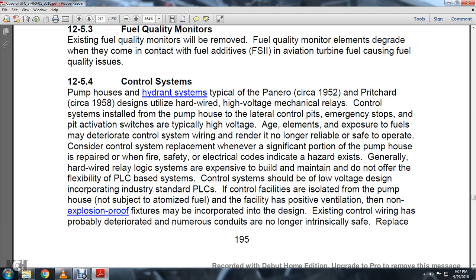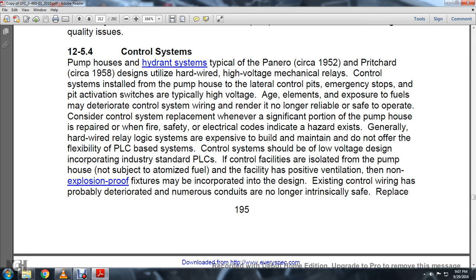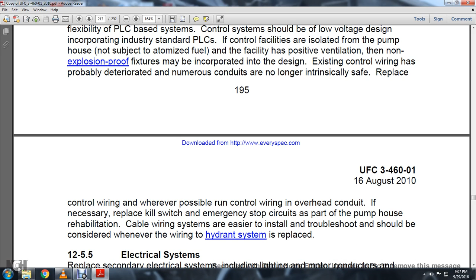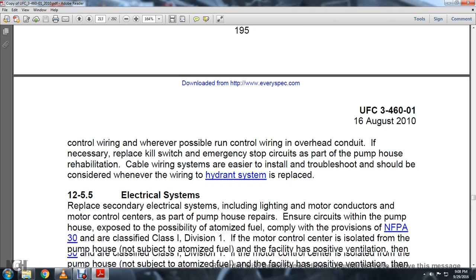Control facilities are situated away from the pump house, not subject to atomized fuel. The facility has positive ventilation, so non-explosion proof fixtures are incorporated in the design. Existing control wire is probably deteriorated under numerous conduits and is no longer intrinsically safe. Replace the control wiring, if possible running the control wiring overhead. If necessary, replace the kill switch and emergency stop circuits as part of the pump house rehabilitation. Cable wiring systems are easier to install and troubleshoot, and should be considered whenever the wiring in the hydrant system is replaced.